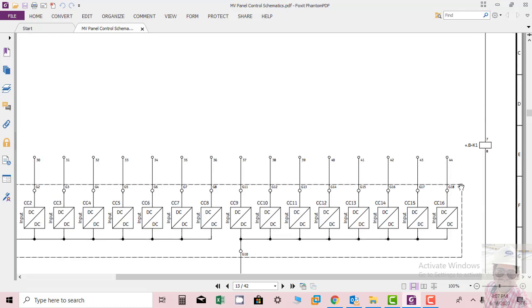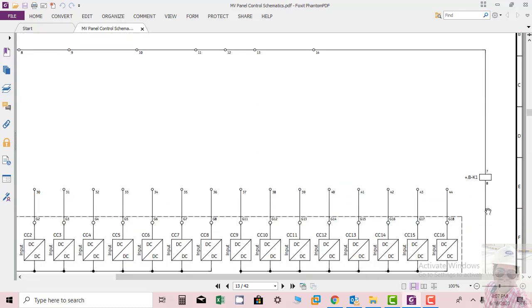So at the end, the relay is installed, which is called a DC supervision relay. Here you can see the BK1 is installed. When the supply is failed, this will give alarm, and contact will operate that this loop DC supply is failed.